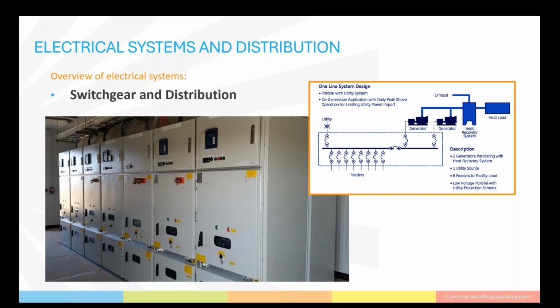Switchgear controls power distribution and consists of breaker compartments and control compartments that can be either separately installed or integrated into one lineup. Regardless of whether you use integrated or separate layout, there are 4 basic breaker compartments for a parallel with utility application. Those compartments are a utility breaker compartment, generator breaker compartment, a tie breaker compartment, which is optional depending on configuration, and a feeder distribution breaker compartment.